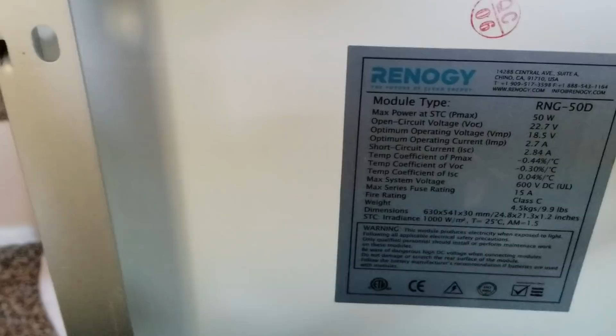If you decide to get 200-watt solar panels, I'd recommend over 300 watts, anything 320 or higher. You can have 290 or whatever, that's fine, but make sure you do the math - not just the VMP, but check the VOC, the highest voltage on the panel, on the back of it. That's what you're looking at. I'll bring a panel here and show you exactly what I'm talking about - here's a clear reference of what I mean.